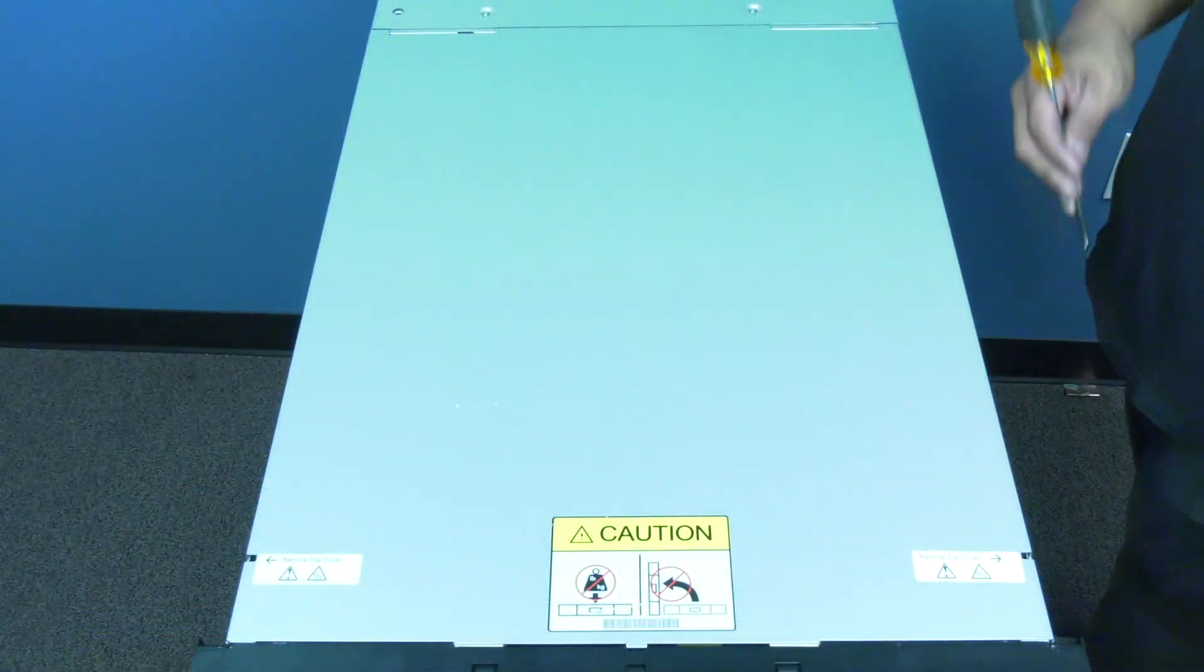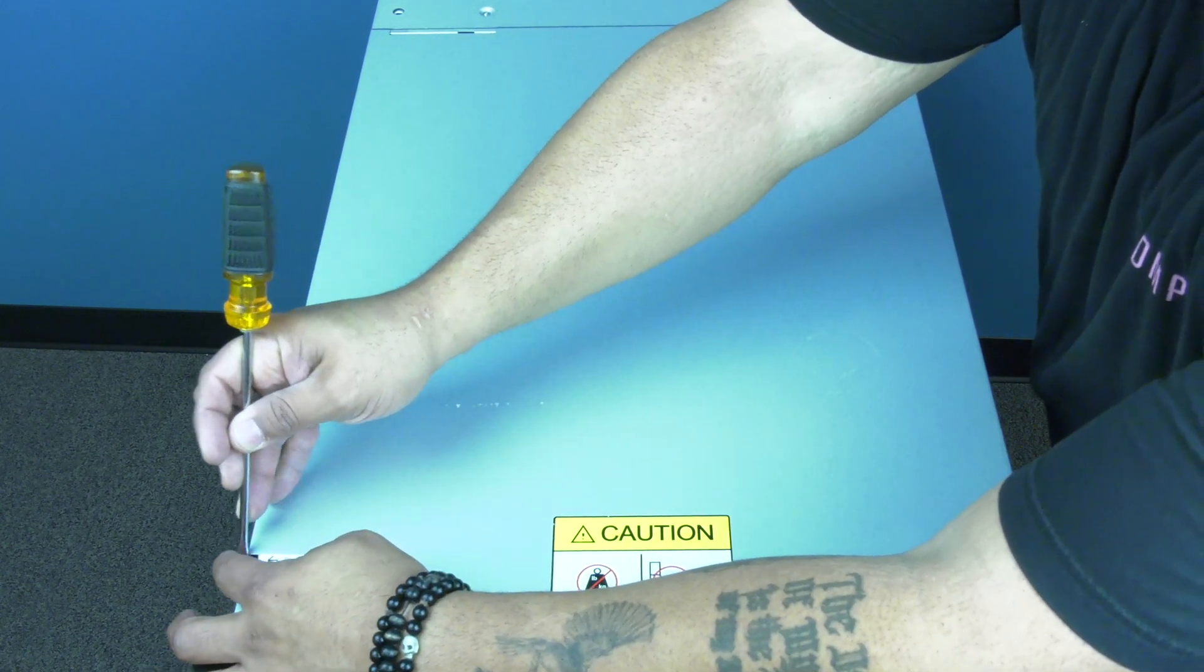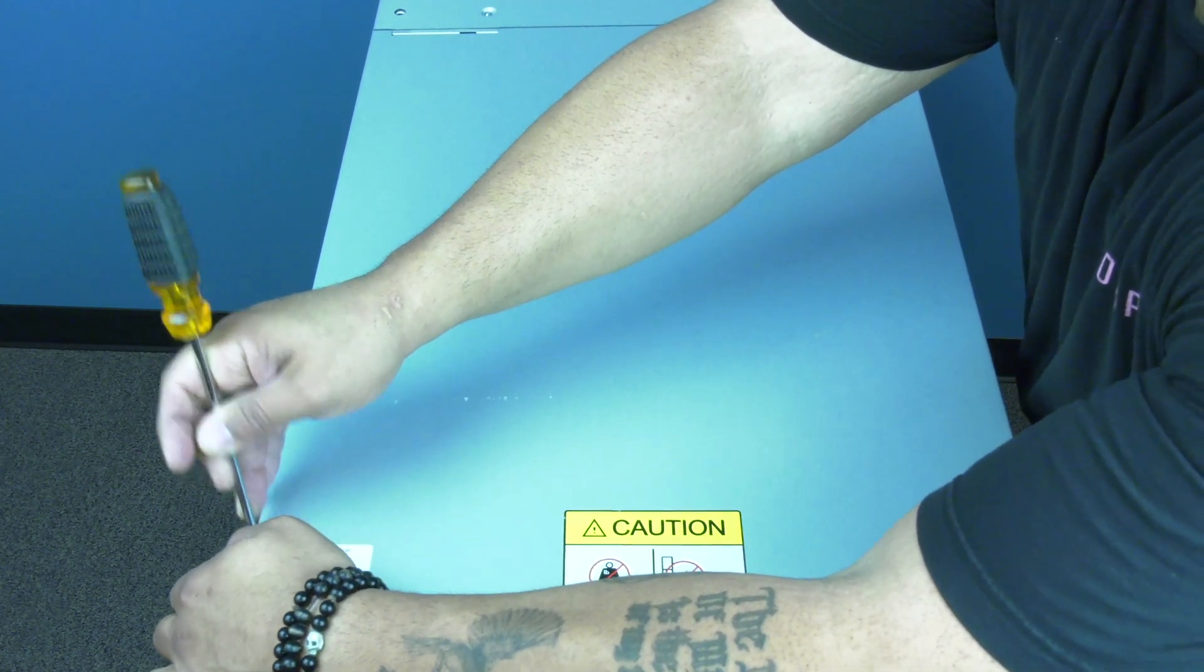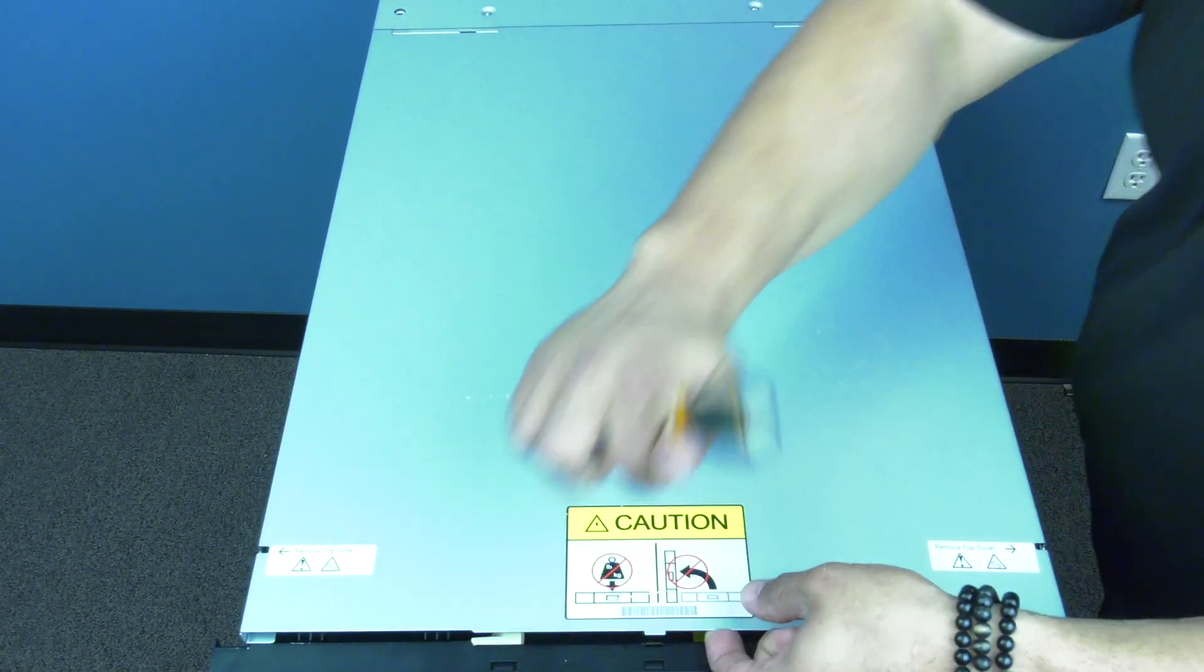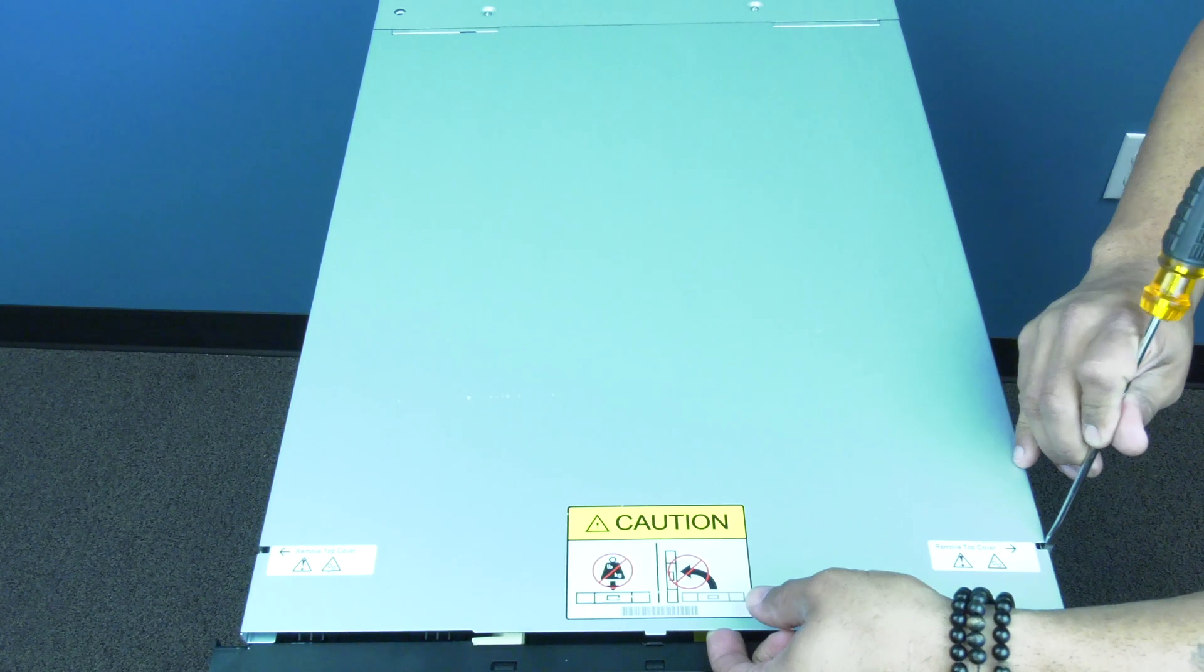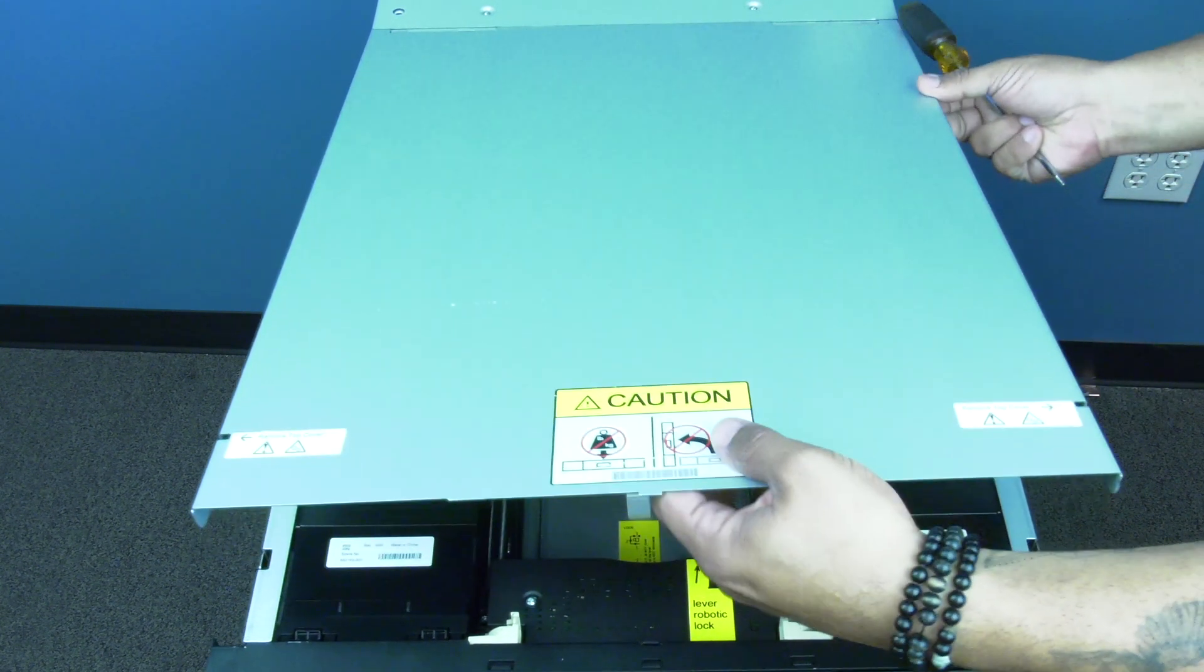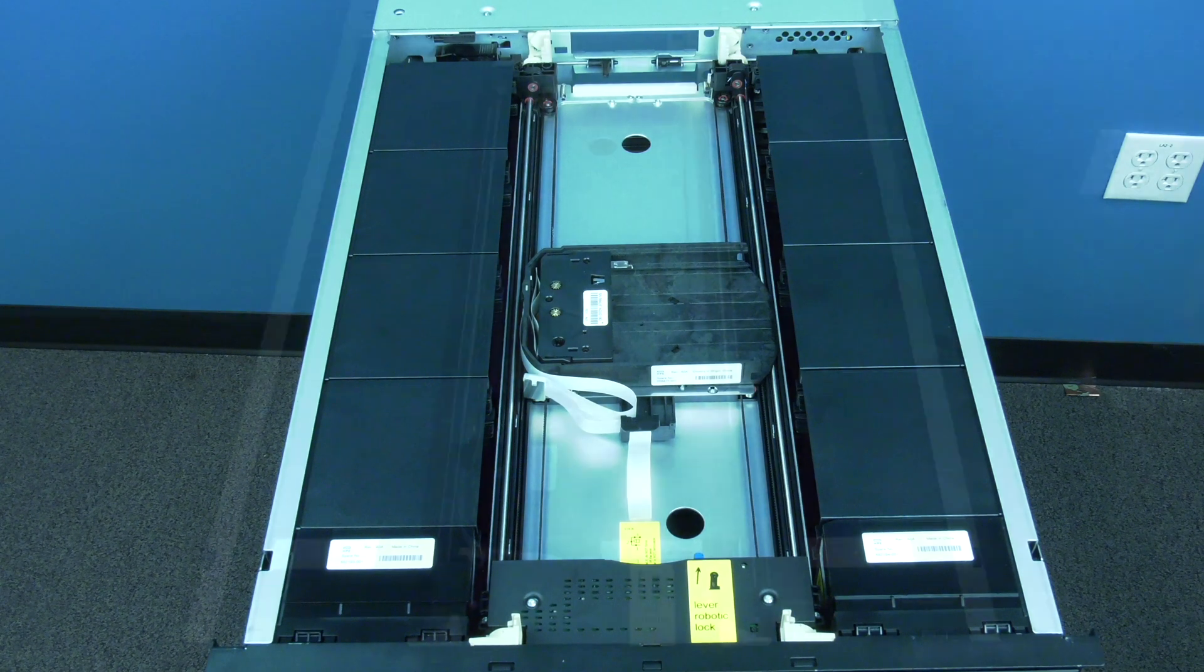Once the control module is on a flat level surface, you can remove the top cover if there is one present. If you have expansions above your control module, you will not have this cover on top. To do this, push a small screwdriver into the hole at the front right to retract the spring lock while lifting up on that corner of the top cover. While keeping this side raised slightly, perform the same procedure to the other side. Then pull the entire front of the top cover up and slide it forward and off the module and set it to the side.